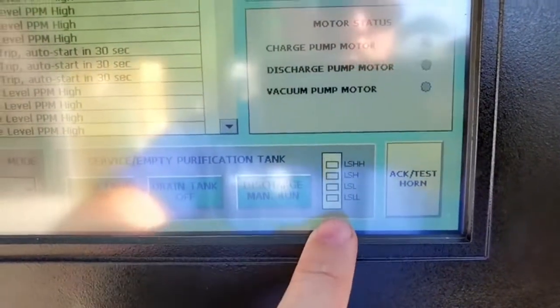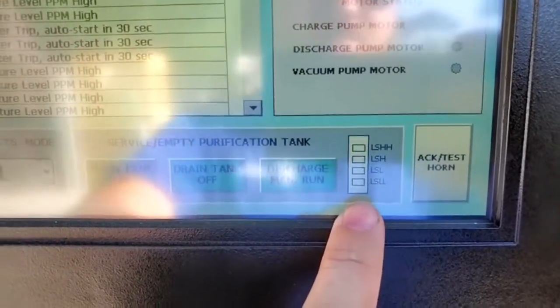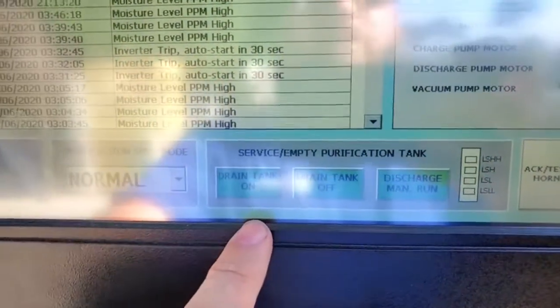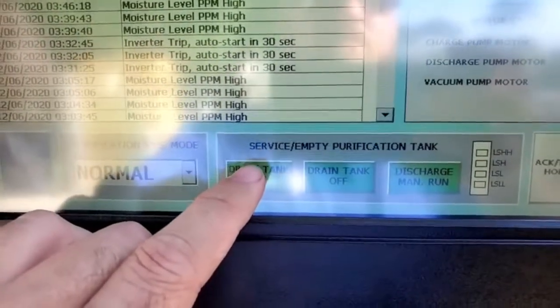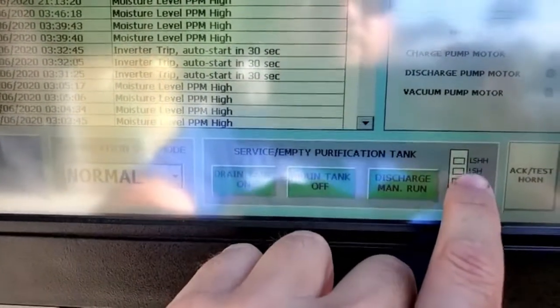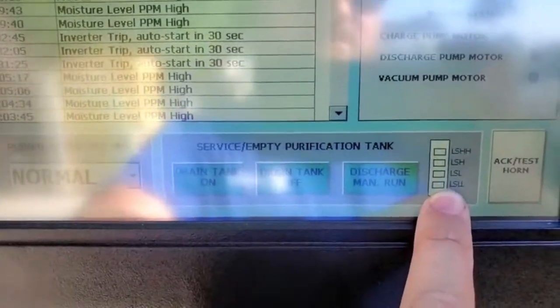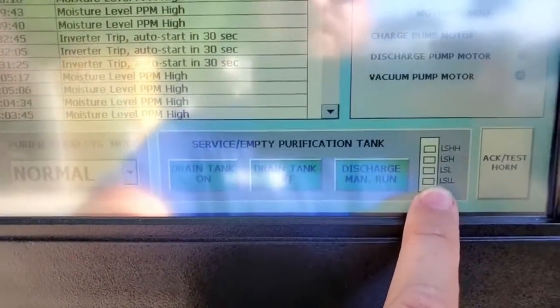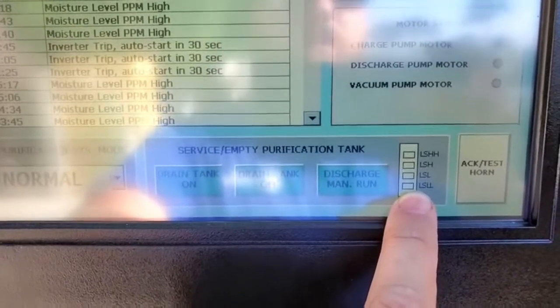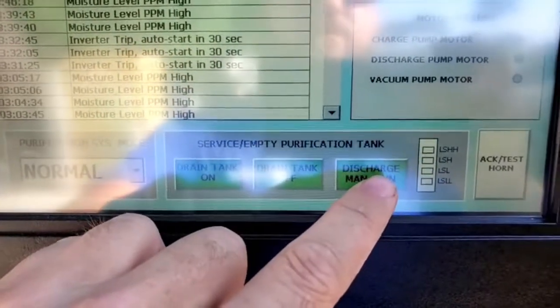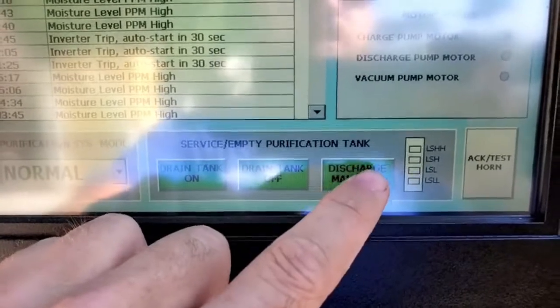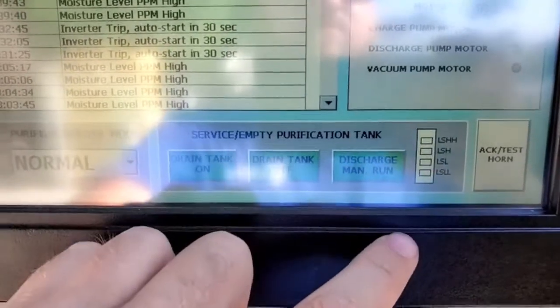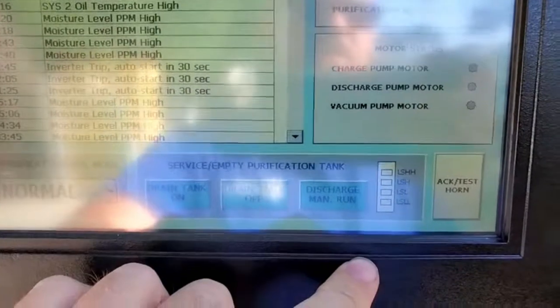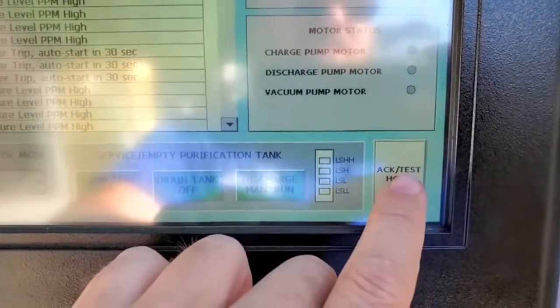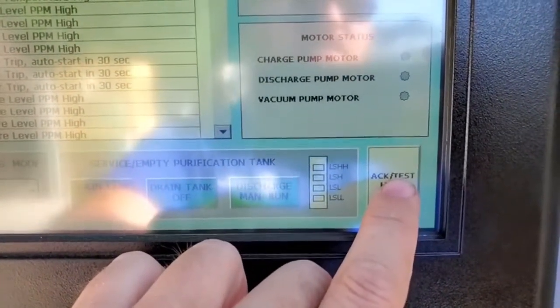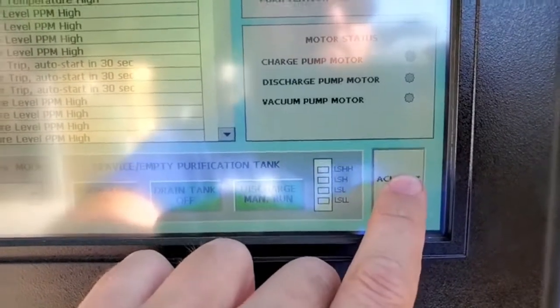Down here again, we have the purification level. And if you need to drain the tank, you can press drain tank on and it'll automatically drain the level until it reaches level 1. Once it reaches level 1, it'll stop draining. From that point, if you need to take more fluid out of the unit, manually discharge by pressing this button and holding it until this light goes off. At any time, if the horn sounds, you can press this button to make it stop, and if it is not sounding, you can press this button to test it.